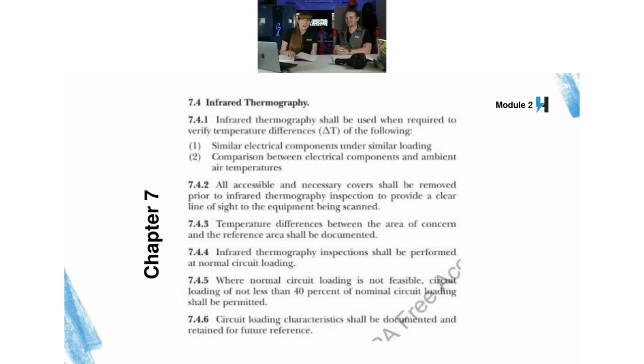7.4, infrared thermography. So it does specify that you have to be able to see everything. So if you're just taking a scan with the door closed, not really going to help you. Nope. Or if you have an infrared window, even better. You want to take direct measurements of the electrical equipment, while under normal load. In fact, it says in 7.4.4, infrared thermography inspections shall be performed at normal circuit loading. If you can't do that, you're not going to be able to get the results that you need in order to have a valid infrared scan.